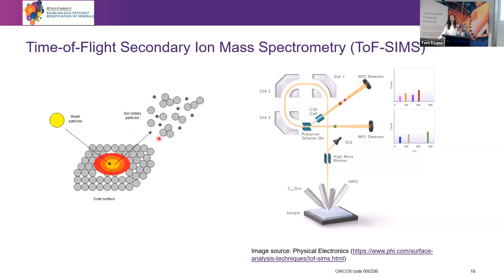These are called the secondary particles that are emitted. The secondary particles are then accelerated to possess the same kinetic energy before entering a flight tube, and they fly through this tube with a velocity proportional to their mass. The heavier particles will take longer to arrive at the detector, so by detecting the different times of arrival, we record a mass spectrum of the particles.